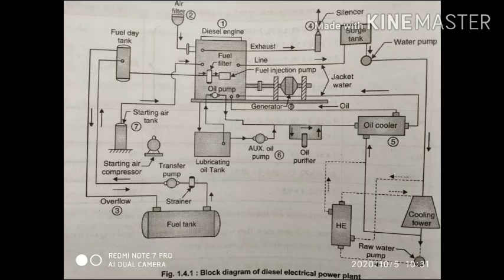The fourth point is the engine exhaust system, including silencers and conducting duct. This system is provided to discharge the engine exhaust to the atmosphere outside the building. The exhaust manifold connects the engine cylinder exhaust to the exhaust pipe provided with a muffler to reduce pressure in the exhaust line and eliminate most of the noise which may result if the waste gases are discharged directly into the atmosphere.